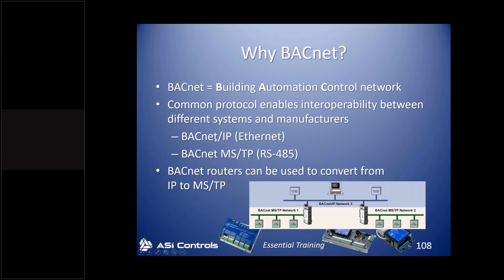BACnet MSTP is BACnet over RS-485. MSTP stands for Master Slave Token Passing. There are also BACnet routers that can convert from IP to MSTP — so a front end that only talks BACnet IP can communicate with controllers that only talk BACnet MSTP through a router. Each sub-network needs its own unique network number. Each ASIC/3 acting as a host controller for a sub-network has a unique MSTP network, and all devices on the same Ethernet network share the same BACnet IP settings, but every router should have a different MSTP setting.